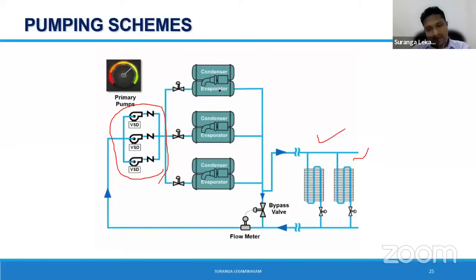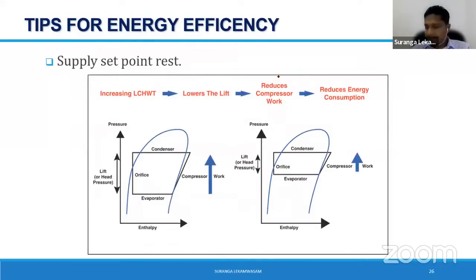If you ask me what happens if the load goes below 50%, then yes, you have to incorporate special controls to fix the flow rate through the pumps and do some bypassing. So eventually, nowadays, you don't see many primary-secondary systems. Instead, you mostly see primary variable systems, which are obviously more efficient compared with primary-secondary.